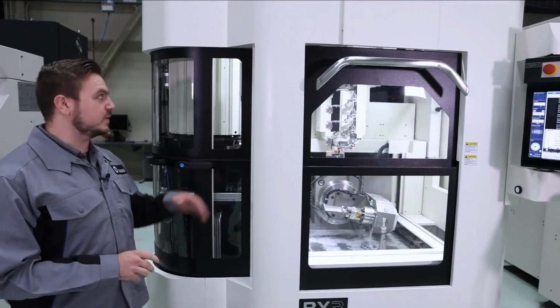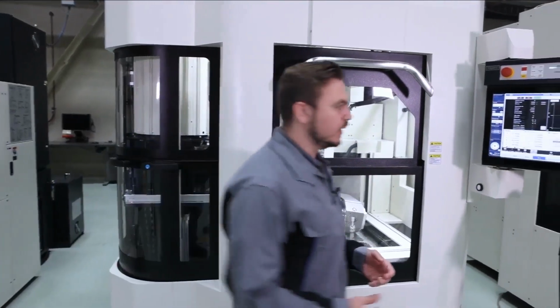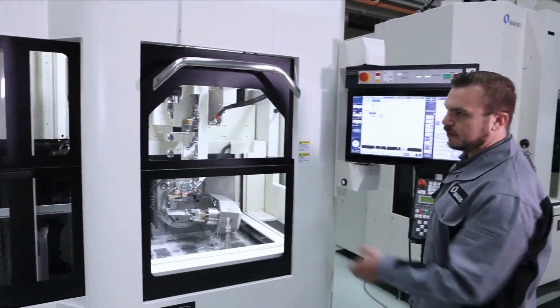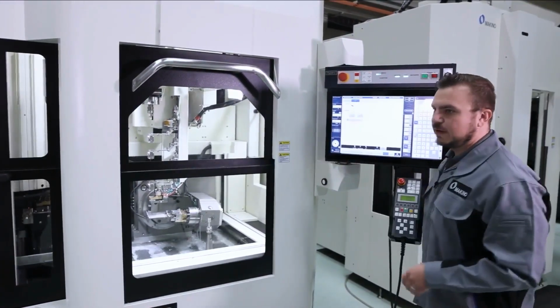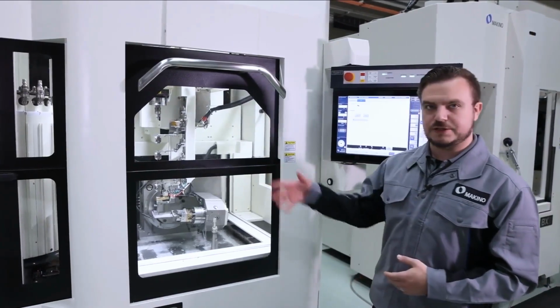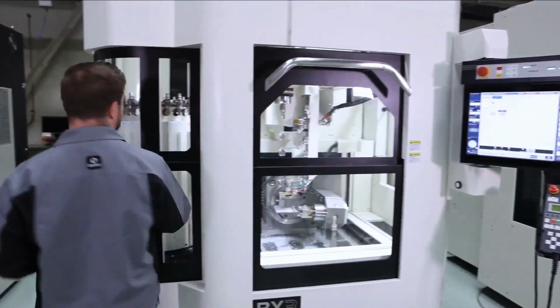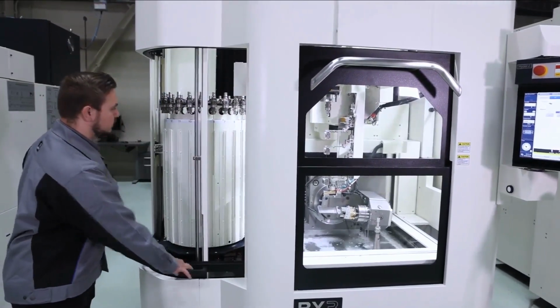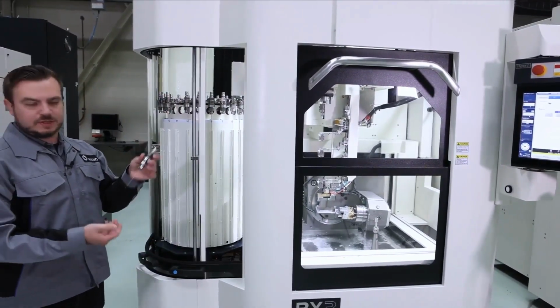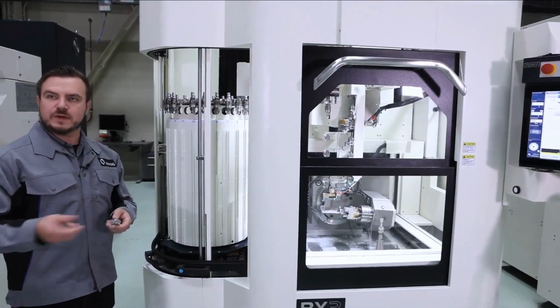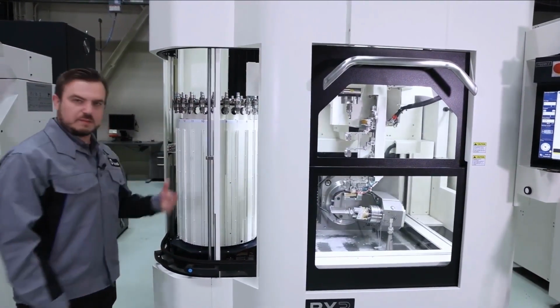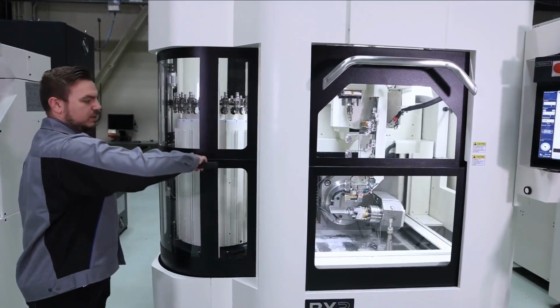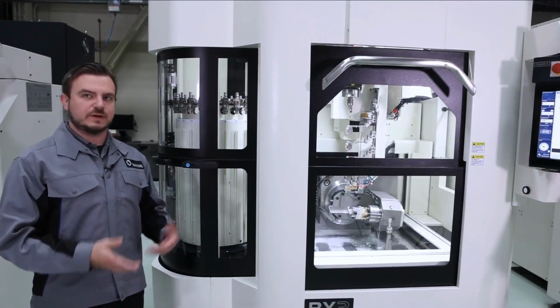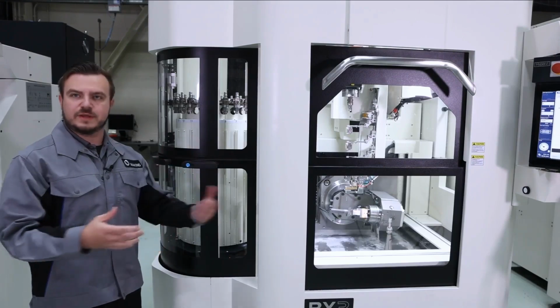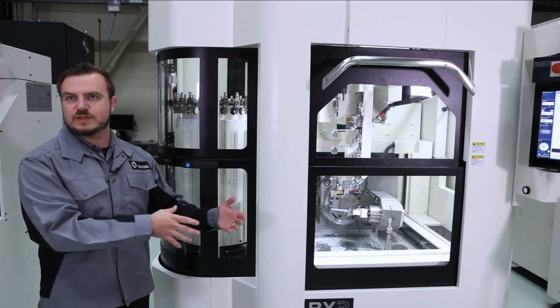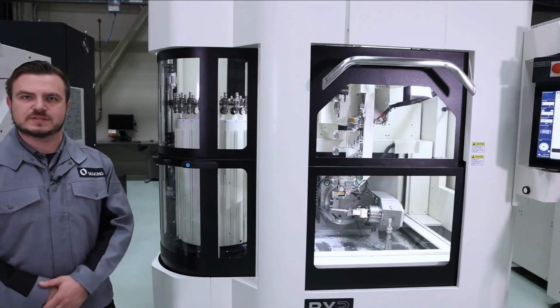So now if I need to replace any electrodes, come back to the control here, and I can lower the carousel. Now this gives me access to the electrodes. So again, I can come over here, open the carousel door, and let's say that I had a spent electrode here. I can undo the clamp, replace the electrode, put it back in the machine, close the door, and when the machine is ready for a new electrode, it'll be ready to grab the replenished electrode. And all that can be done while the machine is in normal operation without interrupting the cycle.